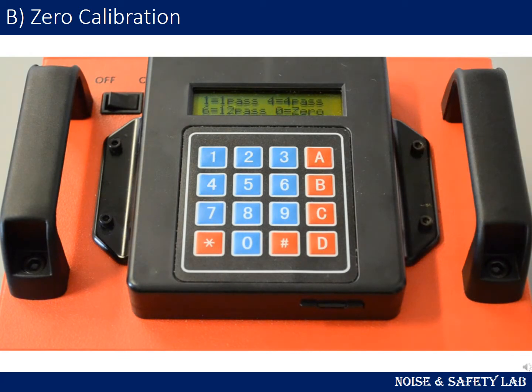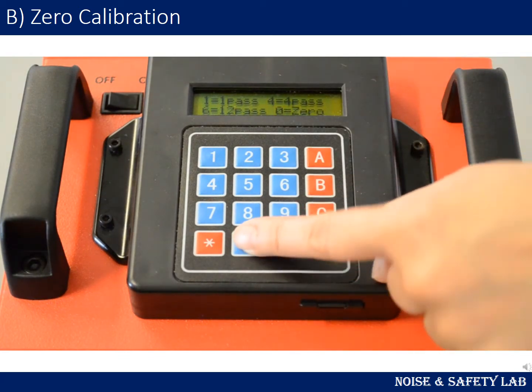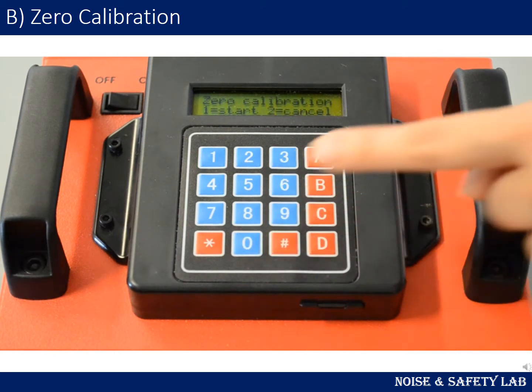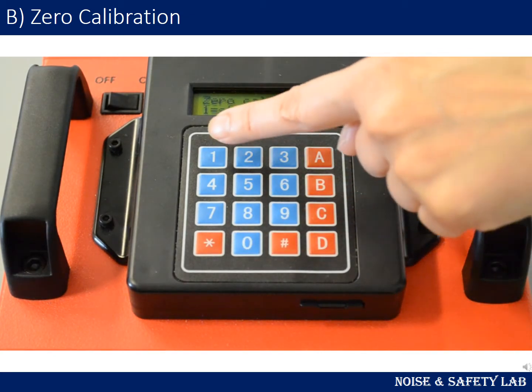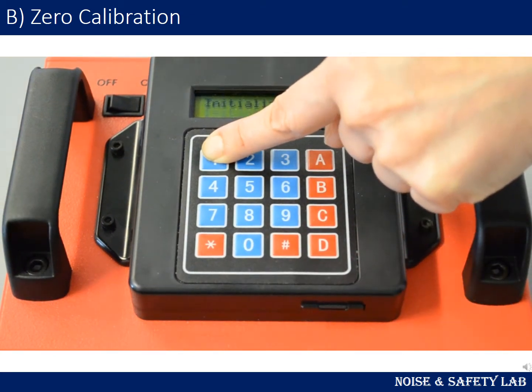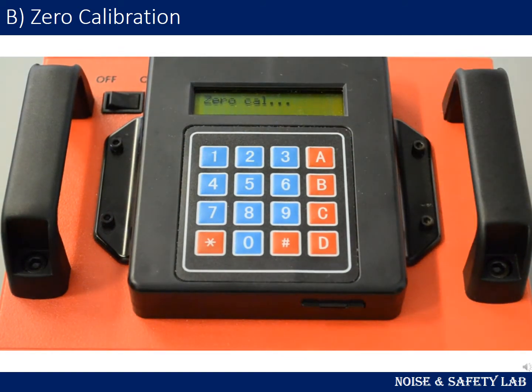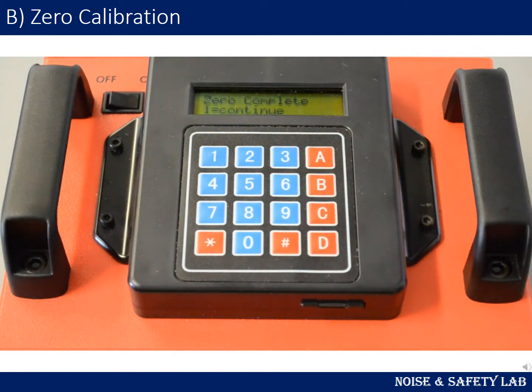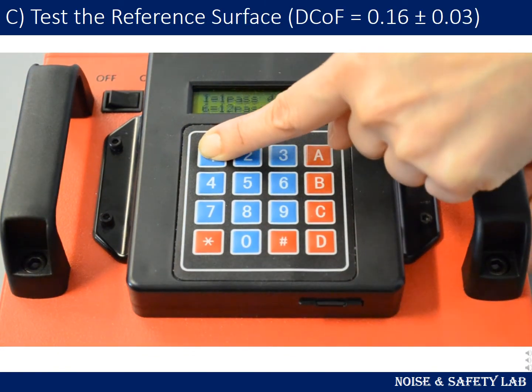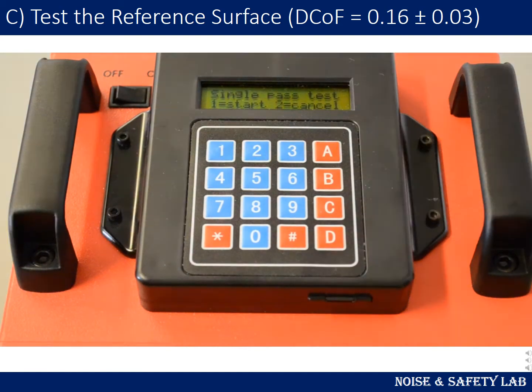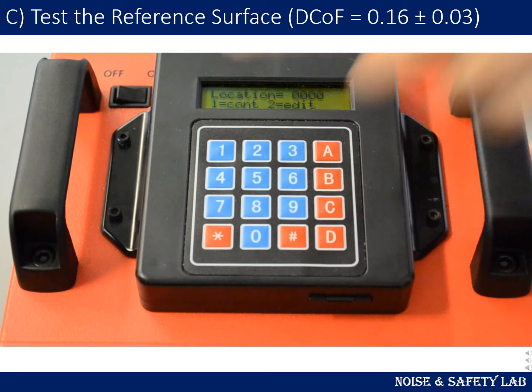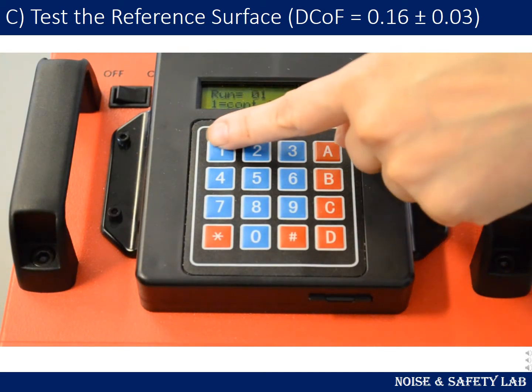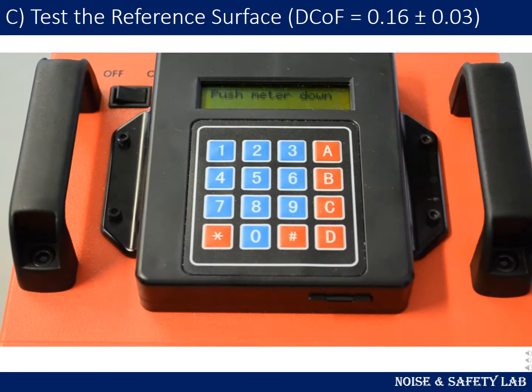Press 0 for a zero calibration run. Press 1 to start the forward and backward travel of the test foot in the air. This travel spreads the SLS solution over the test foot travel area. Then, zero calibration is done. For the reference surface track, press 1 to select single pass test. Press 1 to start and press 1 to accept location number. Press 1 to continue and accept one number.